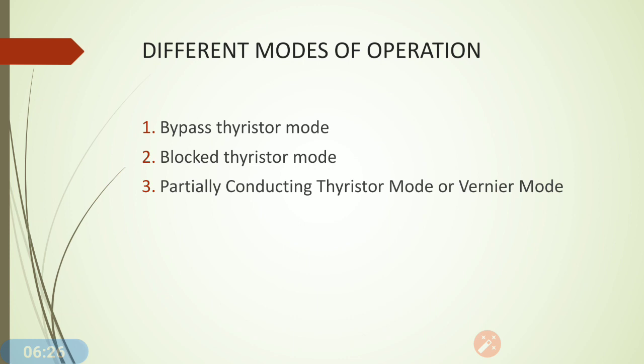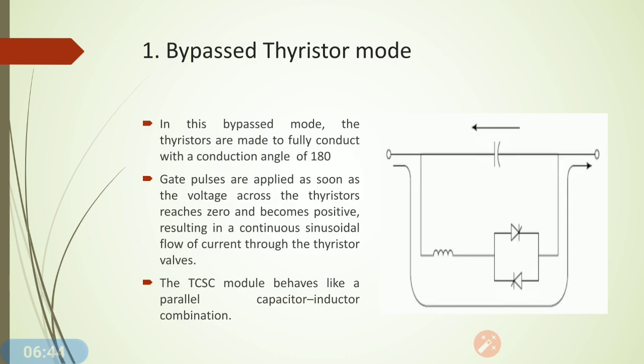There are three modes of operation of TCSC. The first is bypass thyristor mode, the second is blocked thyristor mode, and the third is partially conducting thyristor mode, also called the vernier mode. In the bypass mode, the thyristors are made to fully conduct with a conduction angle of 180 degrees. The gate pulses are applied at 0 degrees of voltage, so when the voltage starts at 0 degrees the thyristors are conducting, resulting in continuous sinusoidal flow of current through the thyristor valve.